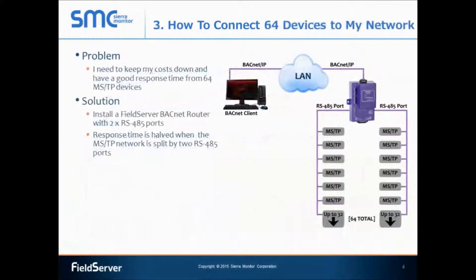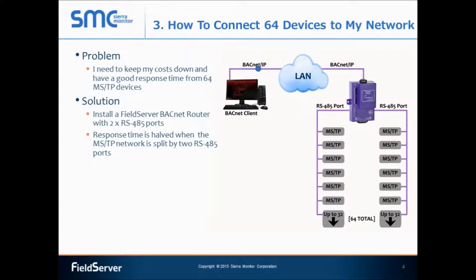Use case number three: how to connect 64 devices to my network. Facilities use BACnet routers to connect BACnet MSTP devices to an IP network. Large facilities often have a large number of MSTP devices and therefore have to deploy multiple BACnet routers, because typical routers usually have a single serial port that connects only up to 32 MSTP devices. As a facilities manager, I have 64 BACnet MSTP devices that I want to cost-effectively connect to my BACnet IP network. The FieldServer BACnet router has two RS485 serial ports, so a single FieldServer BACnet router can connect 64 devices instead of 32. In a large network, this is a cost-effective approach as it can reduce the number of required routers by a factor of two.